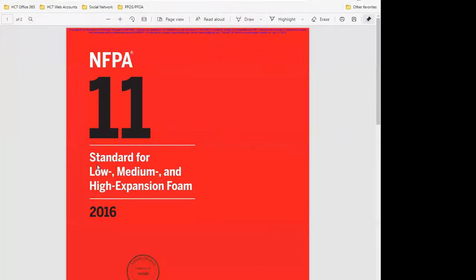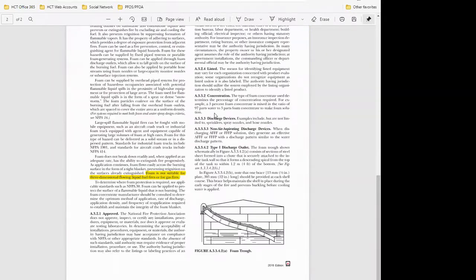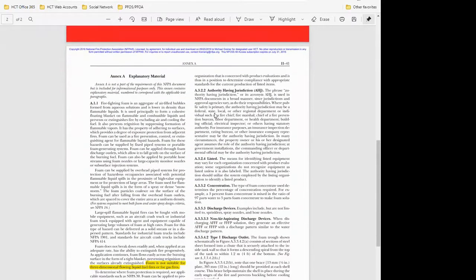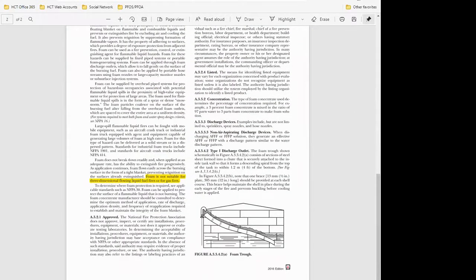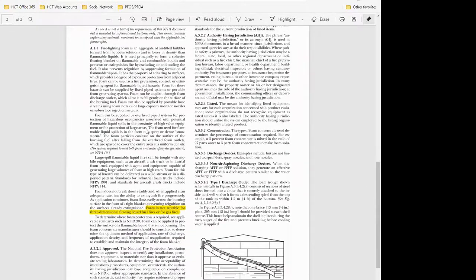And here, when we pull up the NFPA standard, this is the NFPA 11 standard. I hope I haven't messed myself up in the presentation. Here I'm in the Appendix A, A11, and well, I can't blow that up. Hopefully we can see this. It says foam is not suitable for three-dimensional flowing liquid fuel fires or for gas fires. We see foam used in a lot of applications, like flammable liquid rack storage. That's a three-dimensional type fire.